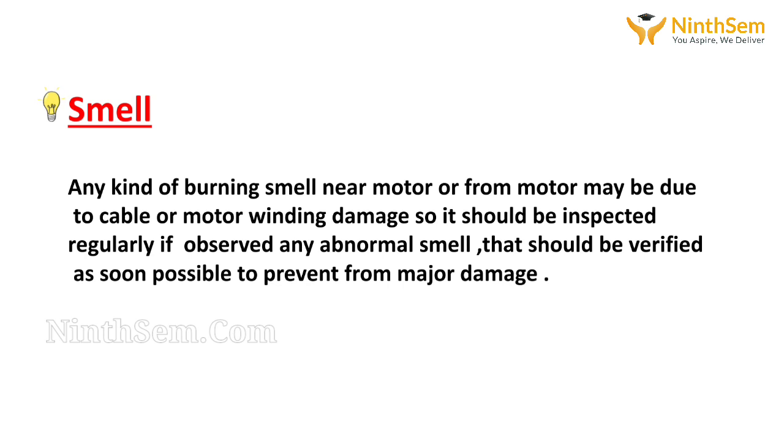The second parameter is smell. Any kind of burning smell near motor or from motor may be due to cable or motor winding damage. So, it should be inspected regularly. If observed any abnormal smell, that should be verified as soon as possible to prevent from major damage.